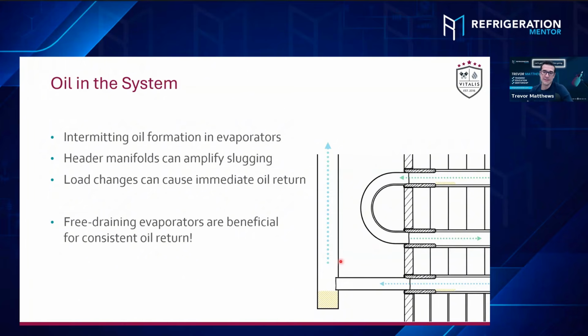Yeah. Oh man. But pretty much the same thing I've talked about before with the liquid line branch off. If you have 5 evaporators sitting on one common suction line and you connect them from the bottom, every single suction line will add some oil into the suction line. And if the closest evaporator to the compressor is connected from the bottom, you would again just drain all that oil into that evaporator, and then you would see those effects as well, right? But that's something that needs to be considered when doing the field piping.